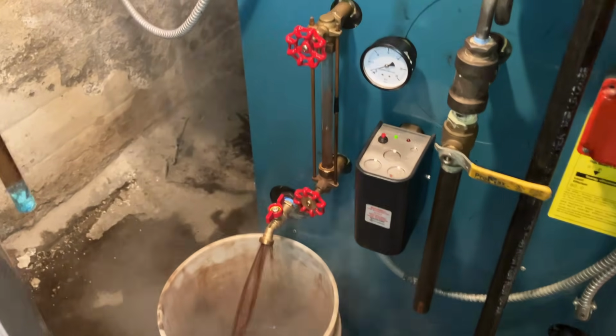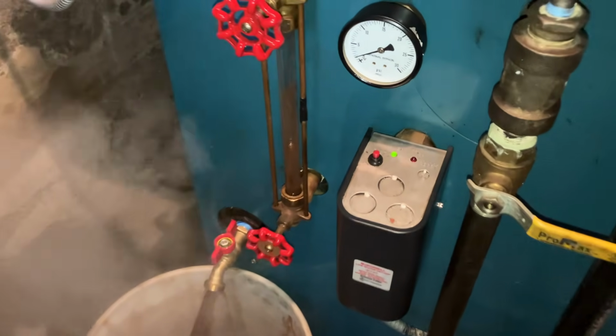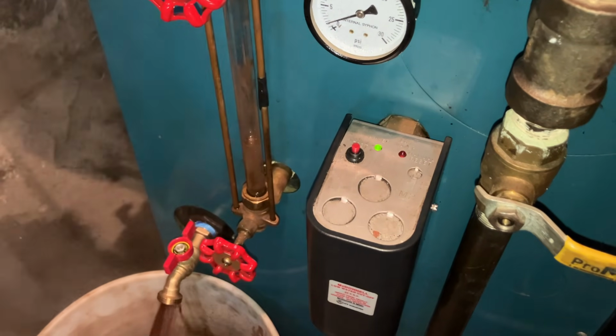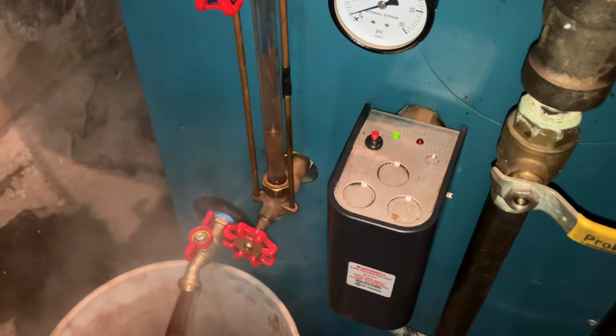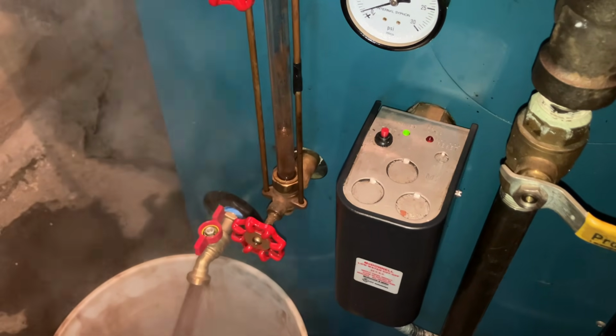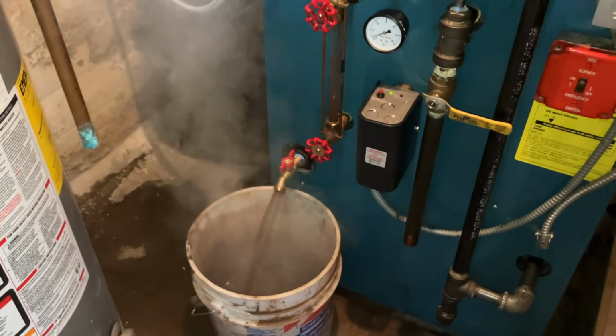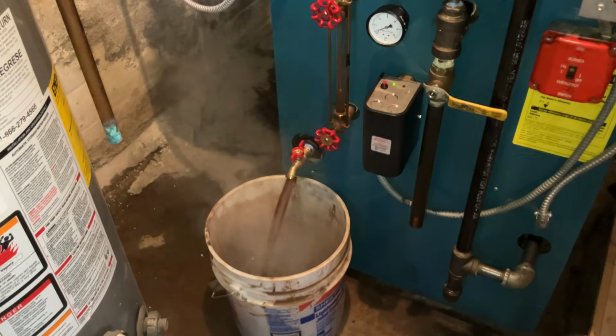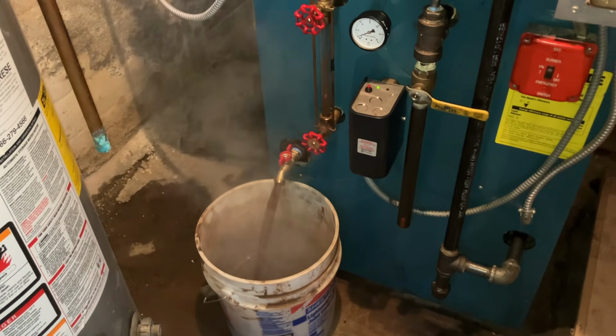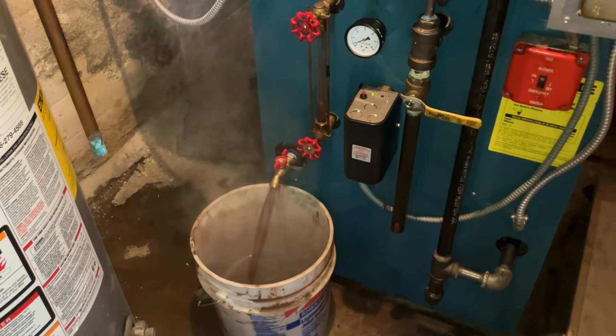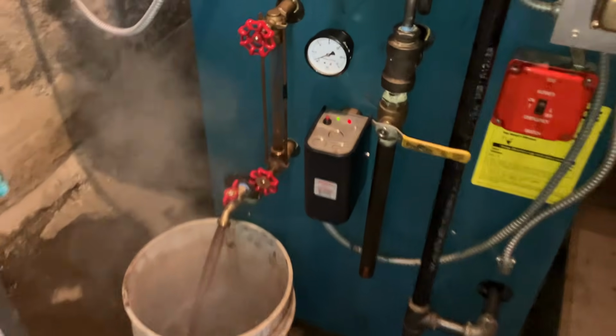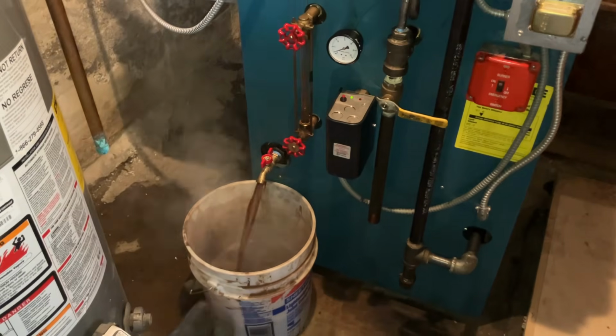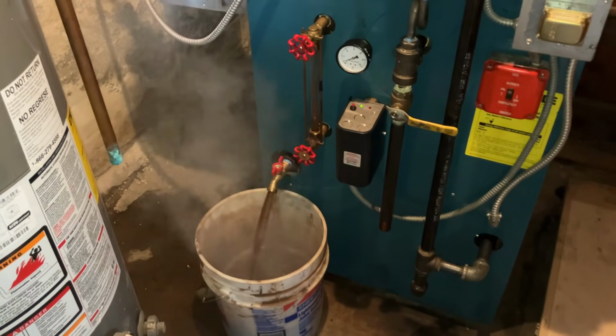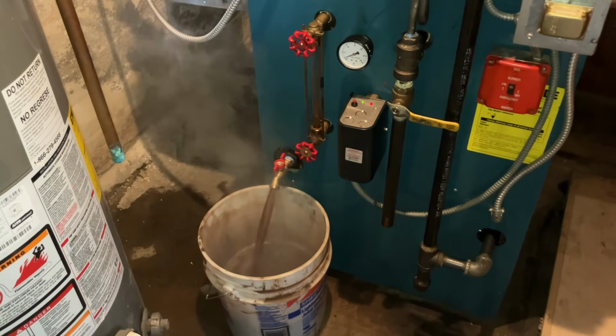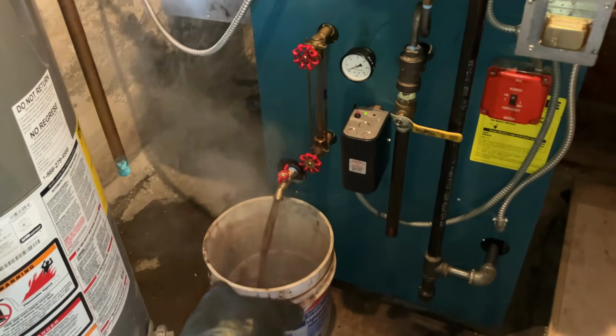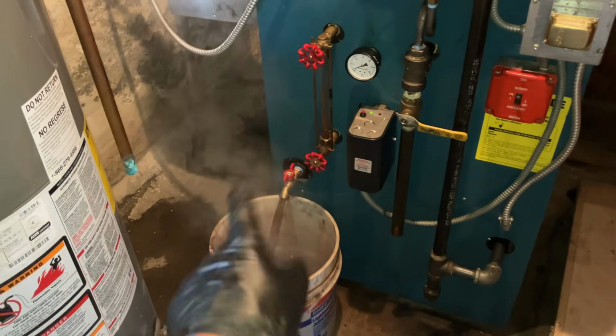Wait for that light to come on. Let's kill that light. We want that red light to come on, the low water cutoff. That water's looking like mud. If you guys are in the trades, plumber, HVAC guy, you service this equipment, remind your homeowners, there's my red light, perfect. Remind your homeowners that clean water will boil at 212 degrees. Do you think dirty water will boil at 212 degrees? Sure won't. You're gonna spend a lot more money to create steam with dirty water than with clean water.